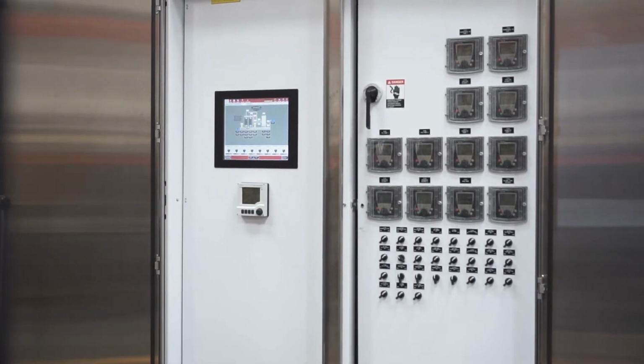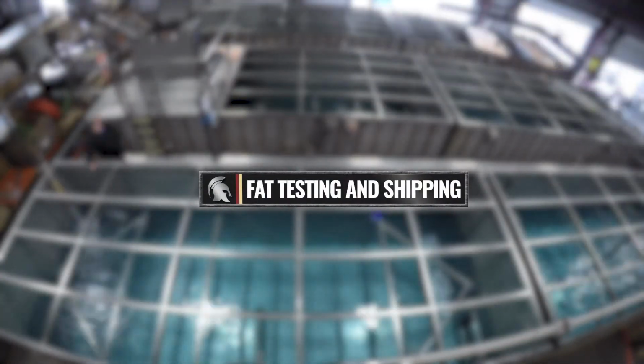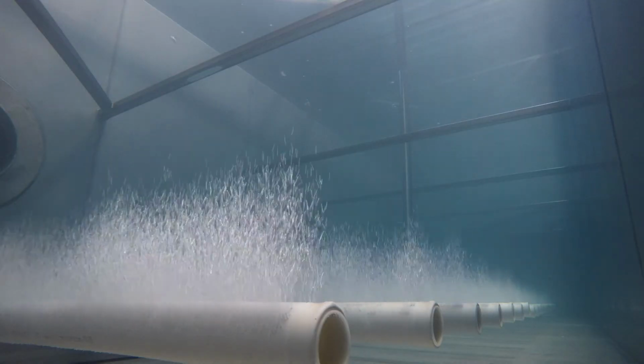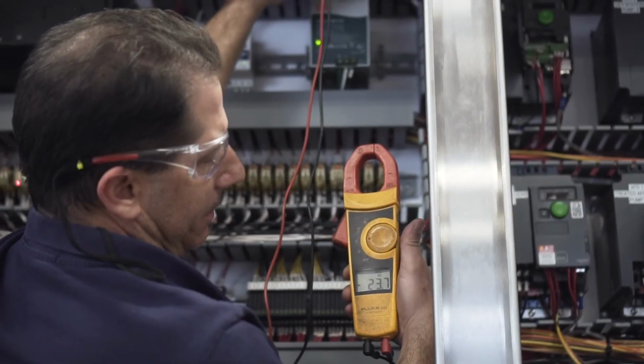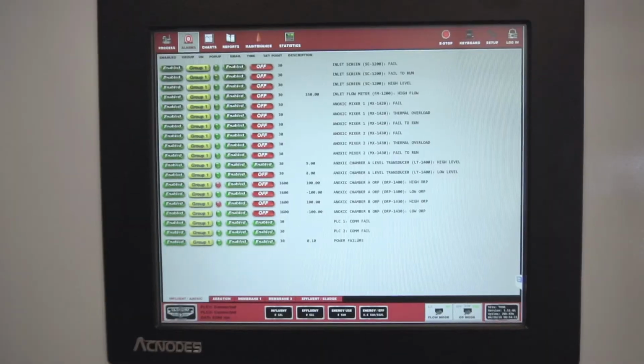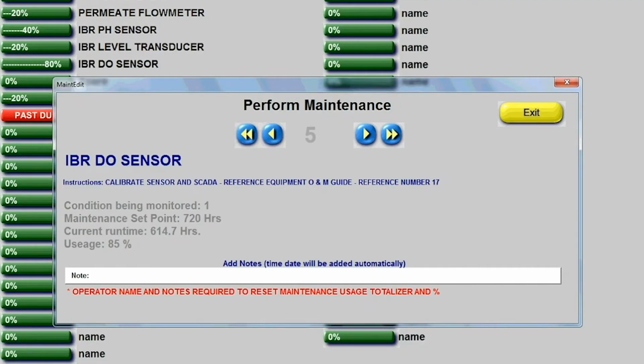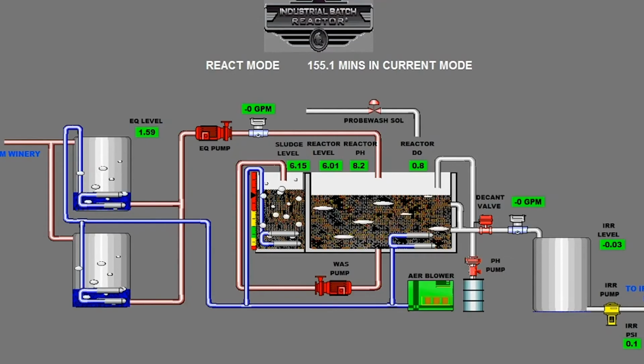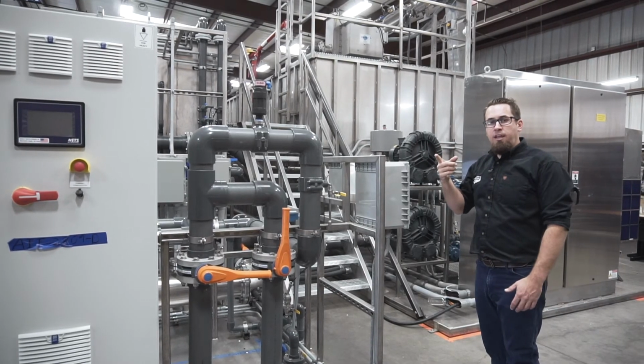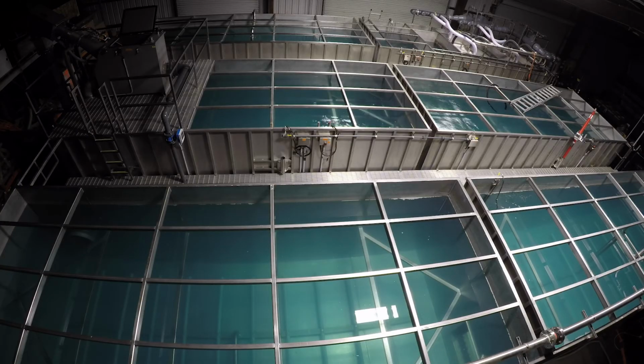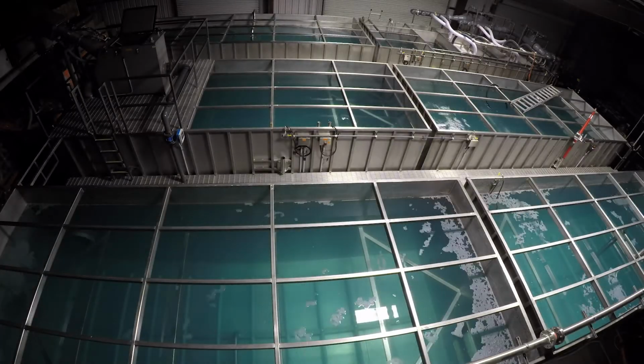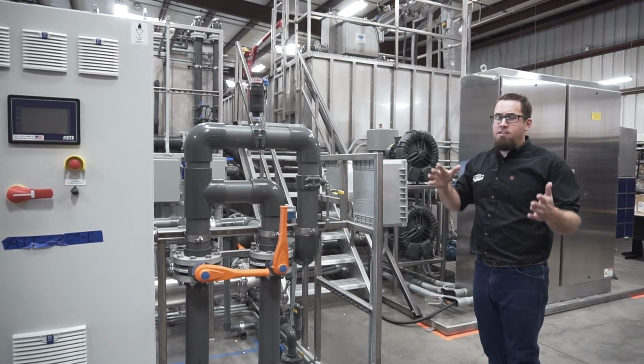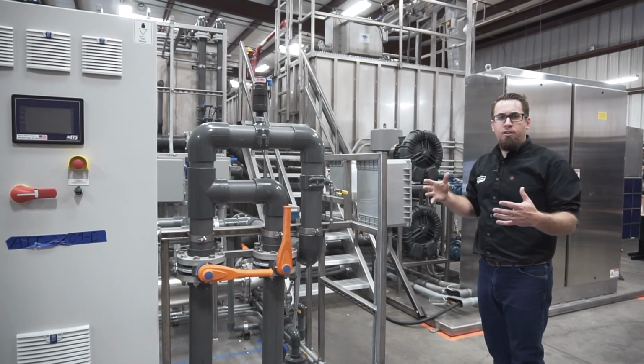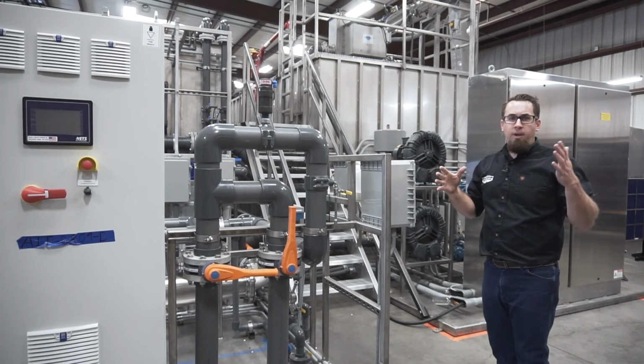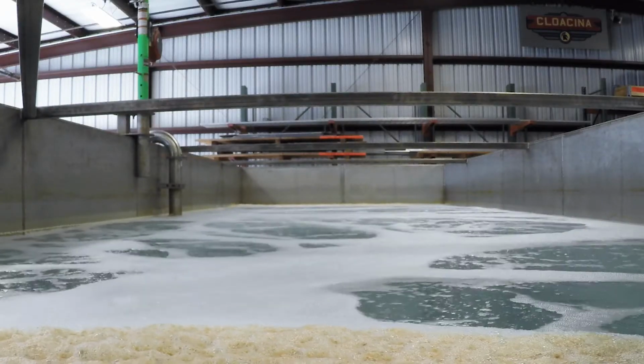These are just some of the standard features that we provide as part of the Cloacina MCC. Right now, we've started the factory acceptance testing process, which is we start all of the pre-checks on all of the pieces of equipment. So we test all of the things electrically, we test all of the things programmatically, and then we move right into an actual hydraulic test of all of the equipment. And we run all of our systems in a loop mode. And then we're able to test them through their diurnal capabilities. We run all of the plants either for days or weeks, depending on how we're tuning things. And it allows us to go from average day flow all the way up to the simulated peak hour flow event.